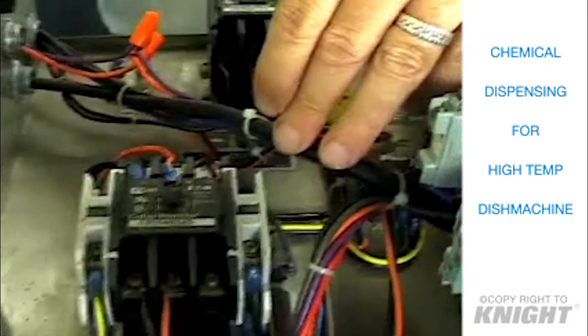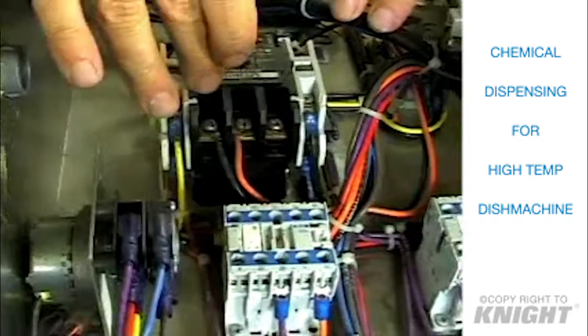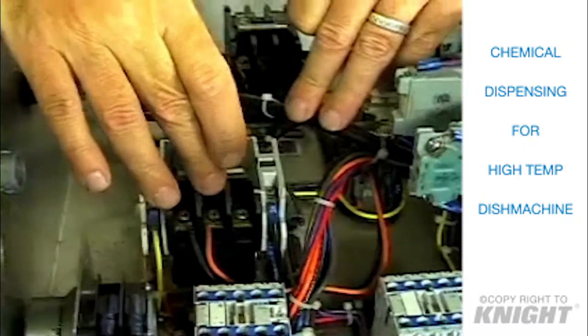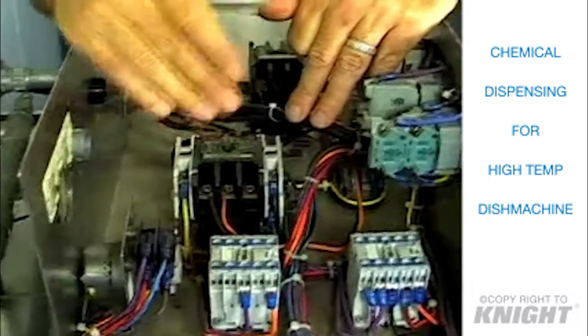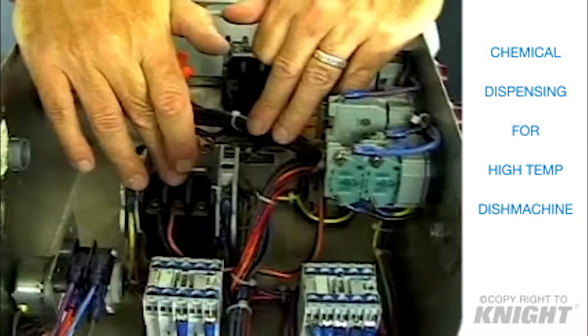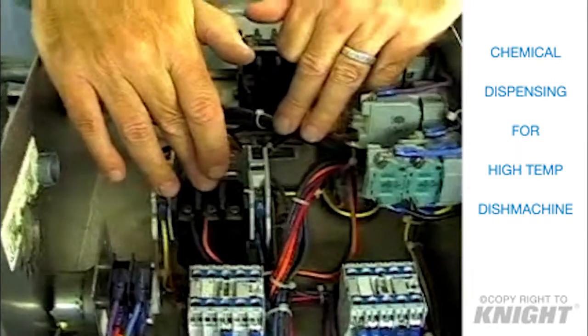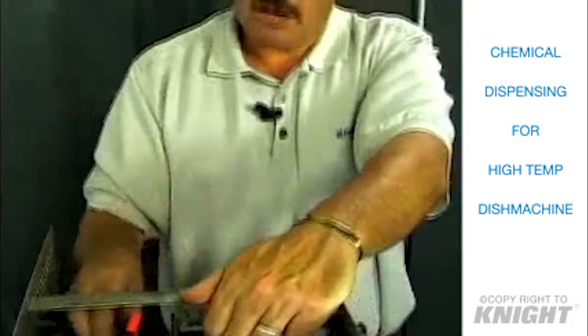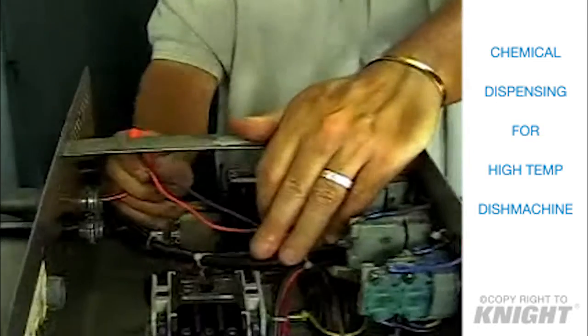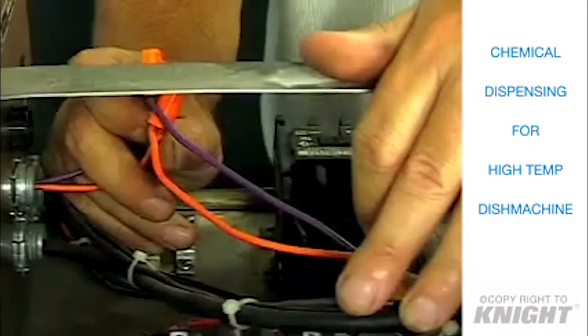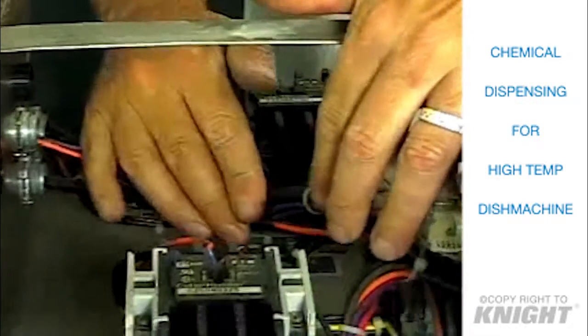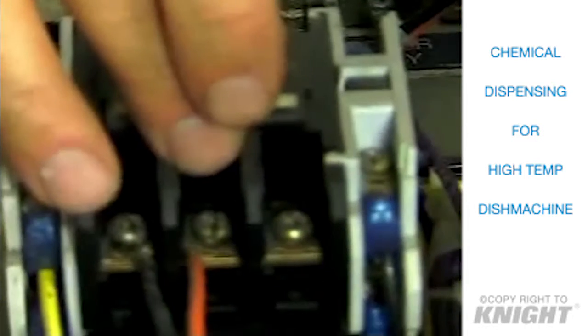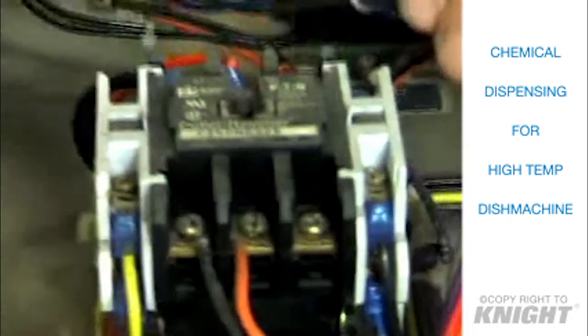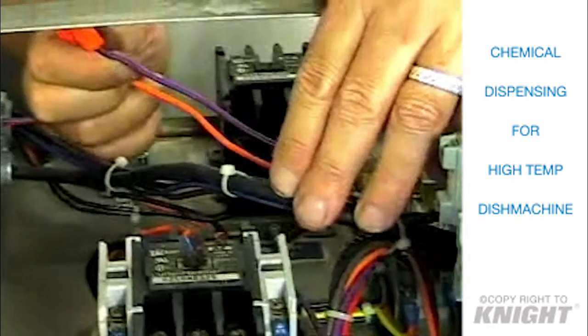And then if we're in probe mode, we just need to go to the T side of the contactor, and when the machine starts the cycle, we'll have power on the T side for the probe operation for 45 seconds, and then on the purple and orange wire to the rinse signal for 15 seconds to operate in probe mode. So our wires would come from line 1, line 2 for our main power to the dispenser, T1 and T2 to the detergent signal, and from our orange and purple wire for the rinse signal.